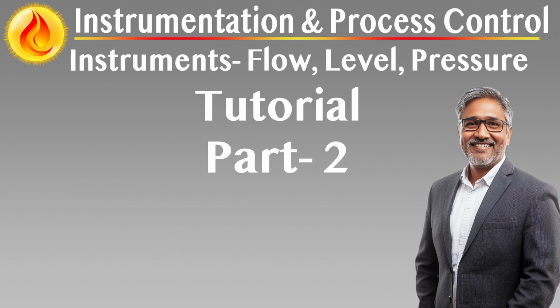Applications justifying diaphragm seals include viscous, waxy, or plugging-prone fluids, e.g. slurries, polymerizing streams, coke-forming processes, where purging or flushing is either unreliable or labor-intensive. High-temperature process media that exceed transmitter or gauge temperature ratings, where capillary isolation prevents thermal damage. Interface measurements in small span ranges below 50 millibar, where traditional impulse lines are unstable or unresponsive.